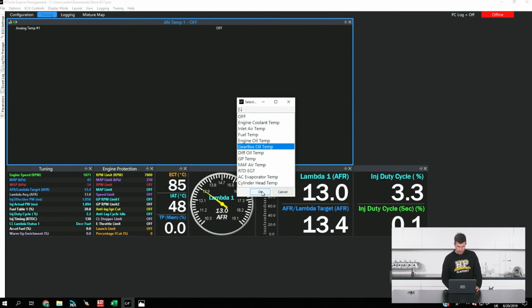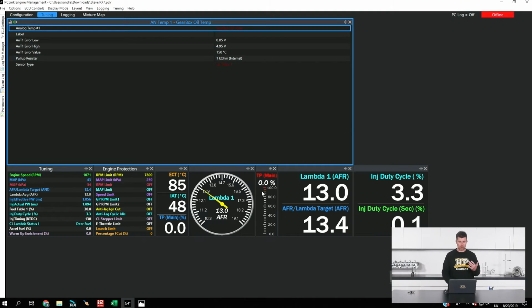So let's choose that option, and this will give us all of the other options that will now become available. We can set an error voltage level. This is just some diagnostics. If the circuit is open circuit, closed, or shorted to ground, it will trigger a high voltage or low voltage warning. In both of those situations, we can also select what the default value will go to, in this case 150C.